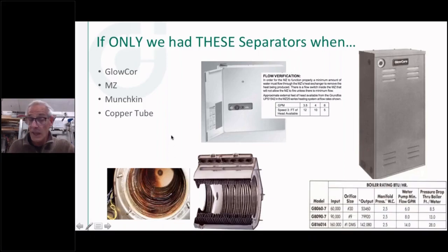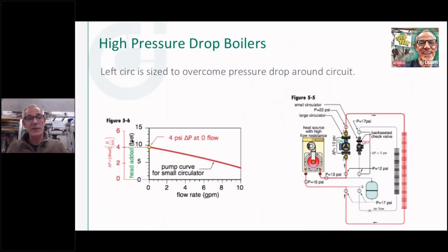So, and really, even some of the copper tube boilers could have done a lot better with primary, secondary piping or hydraulic separators, because they had a bit of pressure drop that you had to make sure that you had covered. So that kind of takes us into primary, secondary. And so let's put some numbers to a high pressure drop type of boiler.